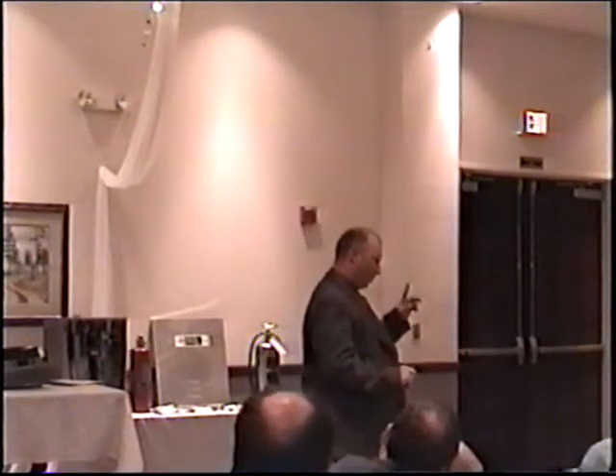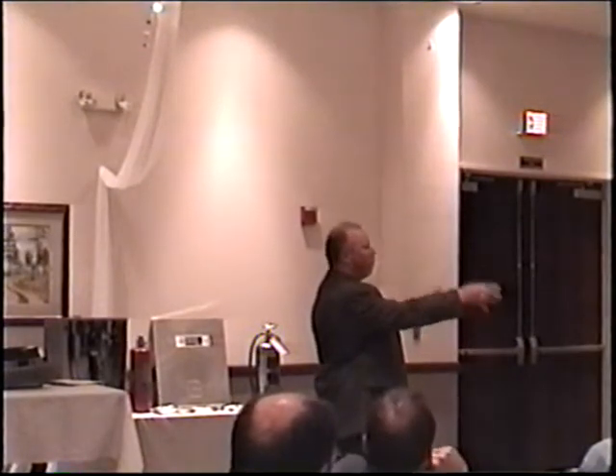Some of the other advantages that I didn't get into too much on the slide projection is the duct protection. The way that the wet agent fire protection systems protect the duct is with a single nozzle into the opening of it. And what that allows us to do is when we service and we pull all the filters out, we can actually see that nozzle. We'll actually take that nozzle off and we'll put a pin through it and we'll actually clean that nozzle.